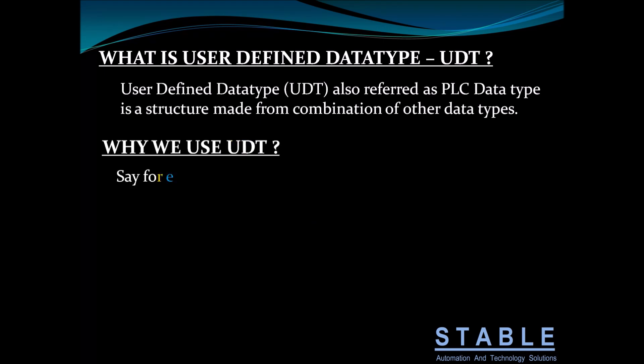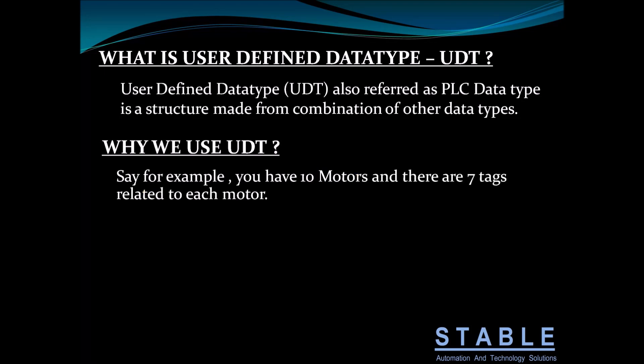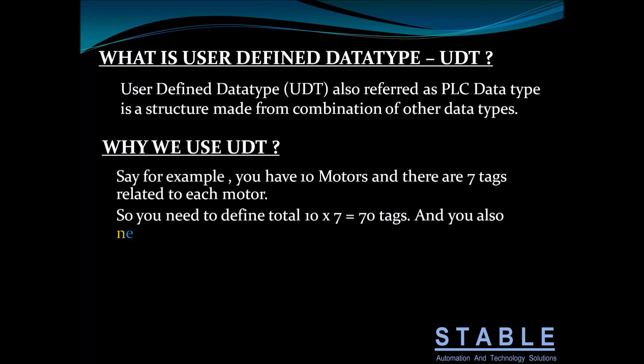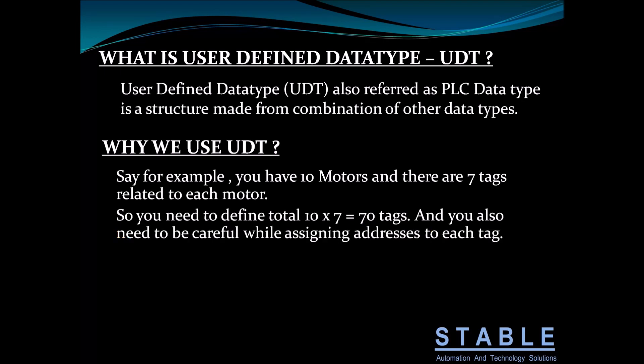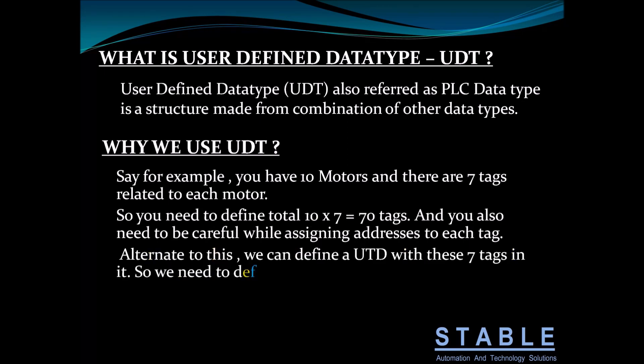Why do we use it? Say for example you have 10 Motors and each motor has seven tags related to it. So you need to define a total of 70 tags and also be careful assigning an address to each tag. As an alternative, we can define a UDT with those seven tags in it, so we need to define only one tag for each motor — that is a total of 10 tags only.